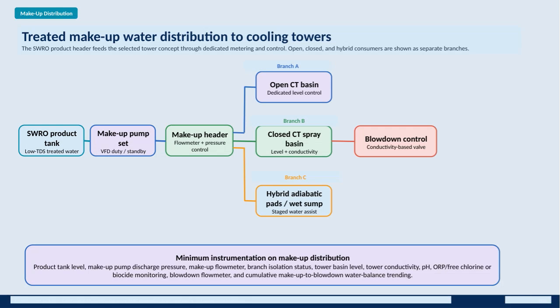This slide outlines a makeup water distribution system designed for the Batum Coastal Data Center, focusing on the integration between SWRO desalination, direct liquid cooling, and the cooling tower setup. The treated makeup water from the SWRO product header is directed to each cooling tower through a dedicated metering and control system, which manages 3 types of consumers: open, closed, and hybrid cooling towers, each represented as separate branches. The system starts at the SWRO product tank, which stores low TDS treated water, then moves to the makeup pump set equipped with variable frequency drives for duty and standby operations. From there, the makeup header ensures accurate flow measurement and pressure control.